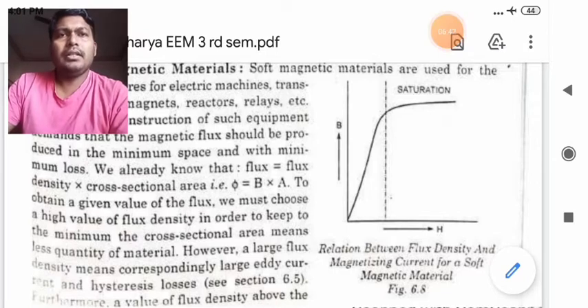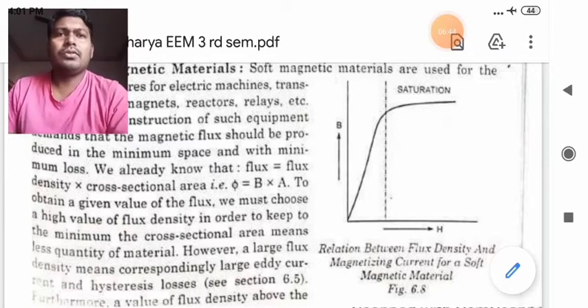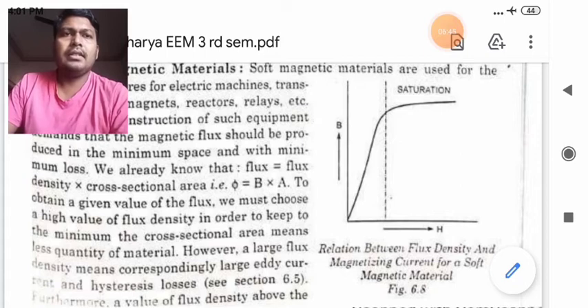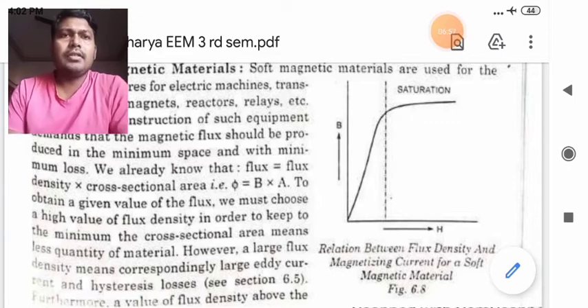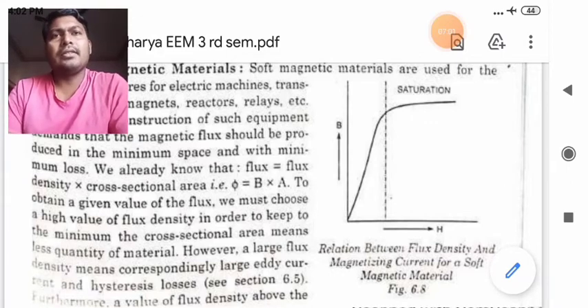To obtain a given value of the flux, we must choose a high value of flux density in order to keep to the minimum cross section area that means less quantity of material. However, a large flux density means correspondingly large eddy current and hysteresis loss.